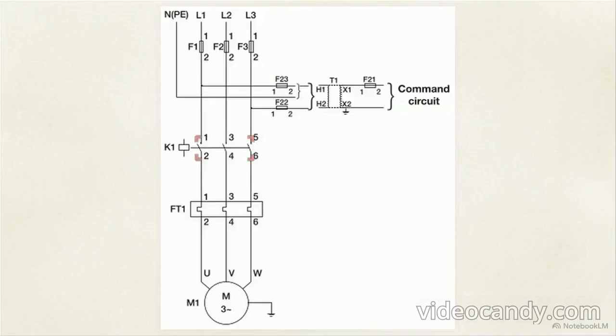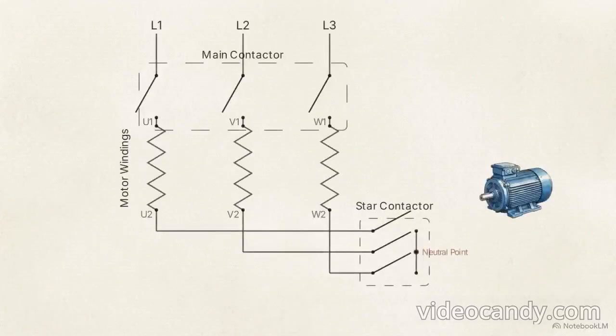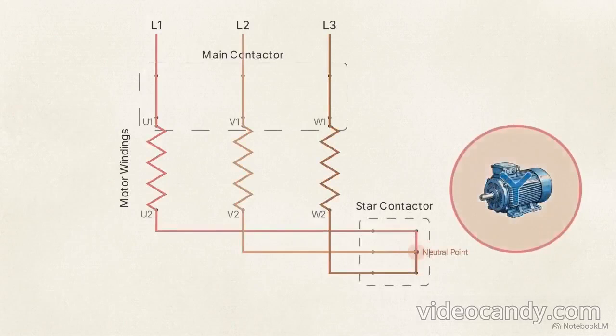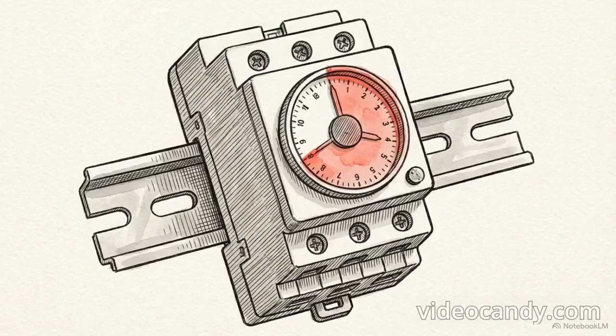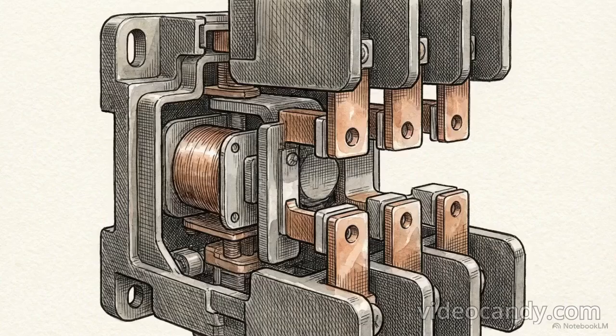The star-delta starter panel is the automated hardware designed to handle this topology shift safely. This schematic outlines the logic required to make the switch. It maps the integration of the main contactor, labeled K1, the circuit fuses, and the critical thermal overload relay, labeled FT1. When the sequence begins, the control circuit simultaneously closes the main contactor and the star contactor, routing power through the U, V, and W lines to energize the motor in the restricted Y configuration.